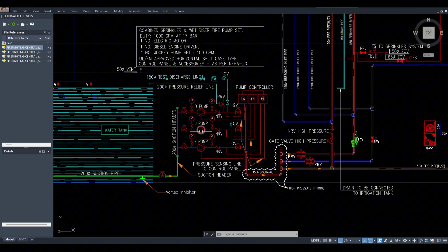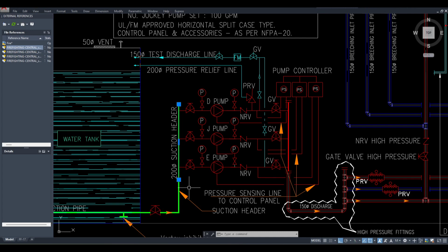No, strainer in fire systems they don't keep because it's not a regularly running system. When it takes the strainer, what does it do? It filters the water to deliver it. So basically in domestic systems we use it, but in fire we don't require it. If you require it at high pressure, when these pumps operate at very high speed for very large demand, the strainer will give a lot of friction to the system. So normally they don't keep it.